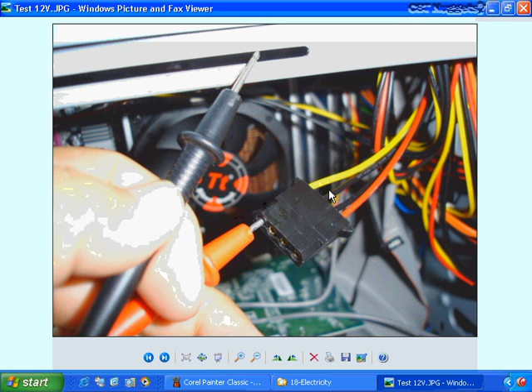Now these two middle cables here, black and black, are both ground. Why didn't I take this probe and put it into the black instead, into that probe right there? The reason is, if these two accidentally touch while I'm testing this, I could have a serious electrical problem. It could short out, melt these, cause an arc, lots of different things that would really rival the time I stuck my finger in a light bulb socket. So I usually go to some other nearby ground where I wouldn't have the risk of accidentally touching these two together while testing.